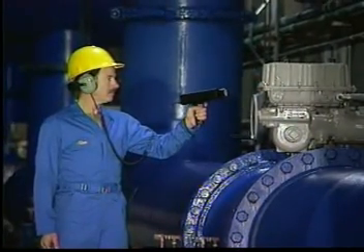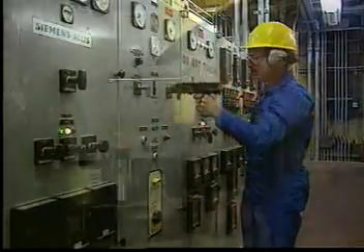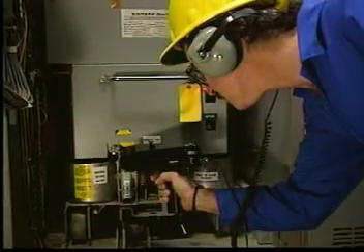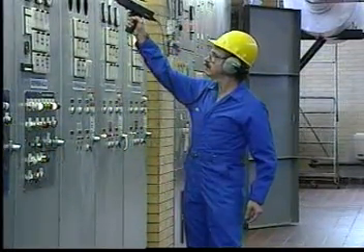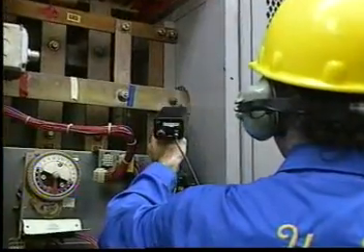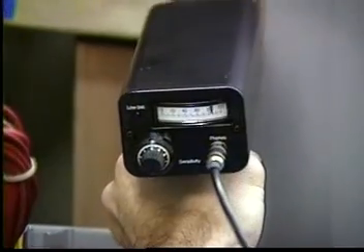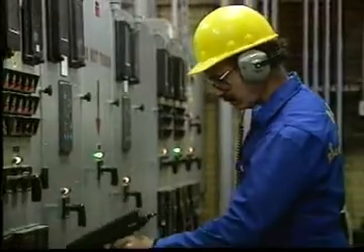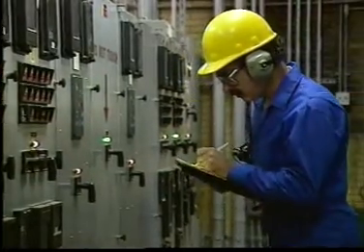There are new applications and techniques devised for the Ultraprobe all the time. Although the majority of applications are for high voltage, there may be situations where it is appropriate to check low and medium voltage equipment — such as connectors, relays and contactors, splices, and occasionally circuit breakers where there may be loose wires or breakers. In low or mid voltage environments, the sounds of electrical discharge will have less intensity. Judgements must be made based on comparisons with other normally operating equipment — the difference between a problem and normal equipment may simply be the difference between a small sound and silence. Establishing a baseline for comparisons is essential to identify a worsening condition, especially at lower voltages where sounds may be less obvious.